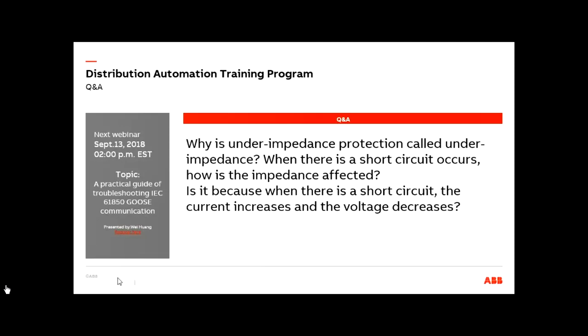And there is another phenomenon here: the terminal voltage of the transformer or the generator might fall because of the fault, but there will be feeding from the external circuit because it's connected to the grid, and there's a contribution from inside the generator as well. So there are two contributions coming in. In any case, the impedance locus moves into the operating characteristic of the relay, and it determines to operate.